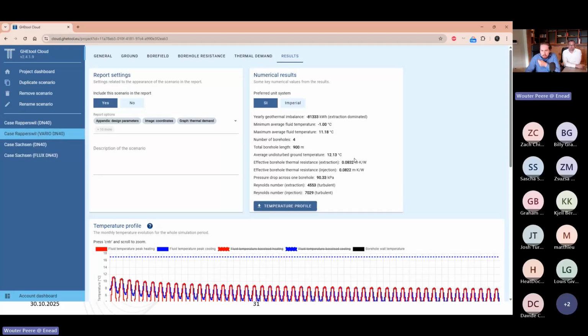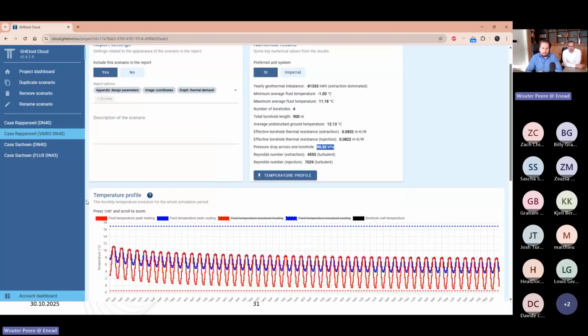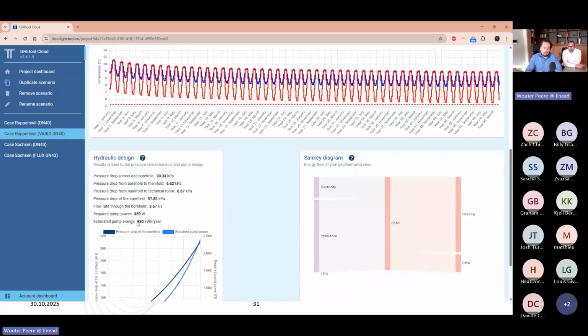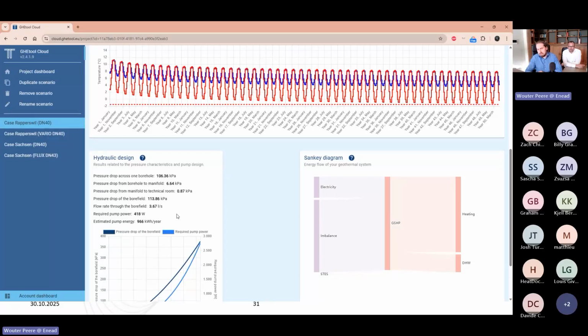And that's because our borehole resistance, as you can see here, is 0.0832. It's a little bit higher here. So our thermal performance from the VARIO is a little bit better. But what's more significant is that here we have only a pressure drop of 90 kPa instead of the 100. And this relates to only having a pump energy consumption of 830 kilowatt hours per year instead of 960.